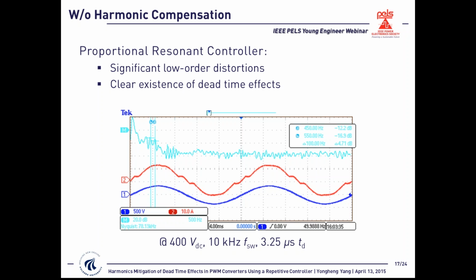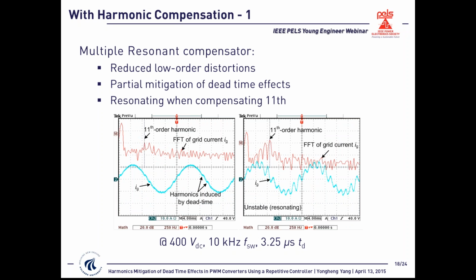There are stairs appearing in the grid current, and this current is not allowed to be injected into the grid because it doesn't meet the grid connection requirement, like the THD should be lower than 5% according to the IEEE standard.